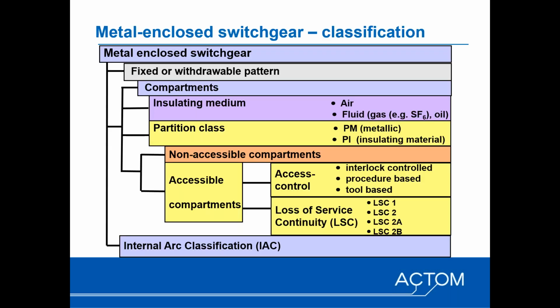When looking at metal enclosed switchgear, which is effectively covered by SANS 1885, just a very high level summary. You've got fixed or withdrawable pattern, as we've covered already. You've got different compartments within the functional unit, different insulating mediums. You've also got a choice between different partition classes, so that's the dividing barrier between different compartments within the functional unit. That can be either metallic or insulating. Then you've got compartments, and there's two effectively types of compartments: non-accessible compartments as well as accessible compartments, and we'll touch on those later and their relevance when it comes to solid dielectric insulated switchgear.